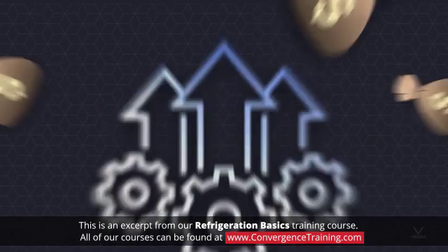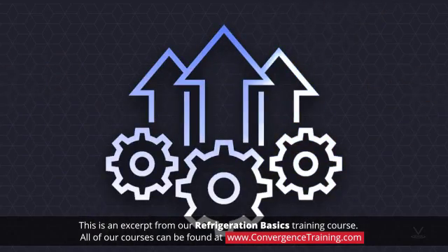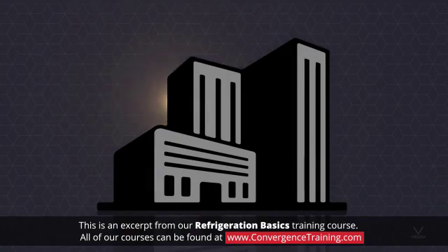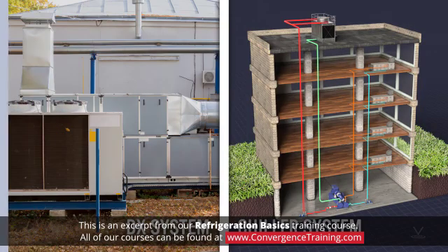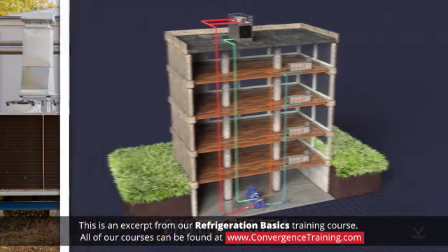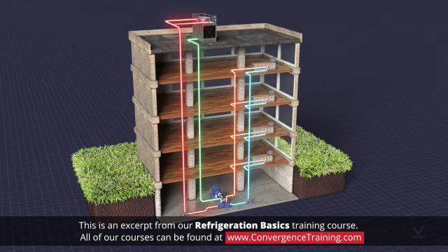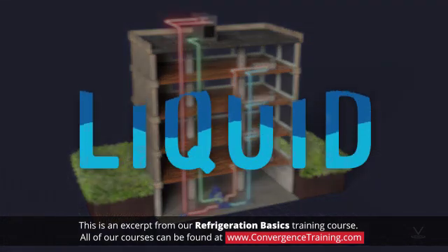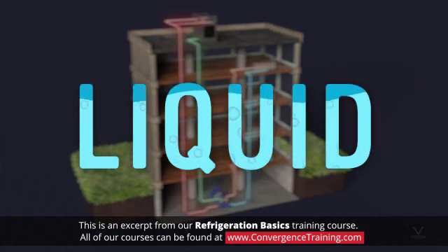Water-cooled chillers are more costly to install but more efficient, so are more often used on larger commercial properties with higher cooling loads. The main difference between DX systems and chiller systems is that chiller systems have one or two extra water loops involved in the heat transfer process. Because the refrigerant receives thermal energy from liquid water instead of air, a different refrigerant type of heat exchanger is used.